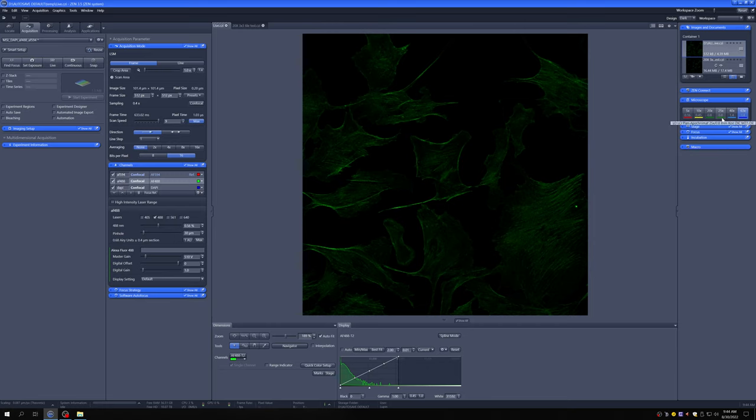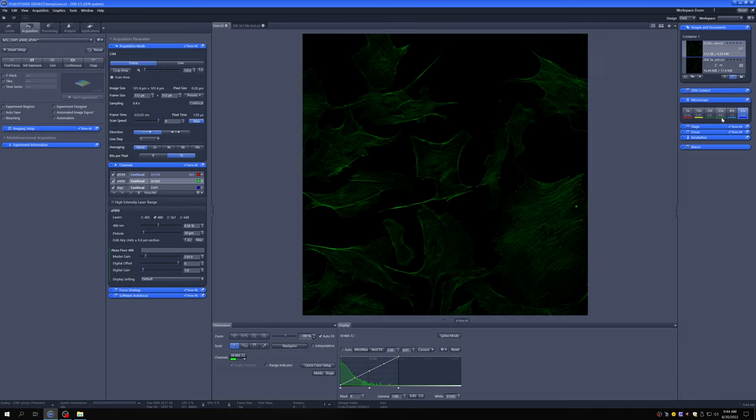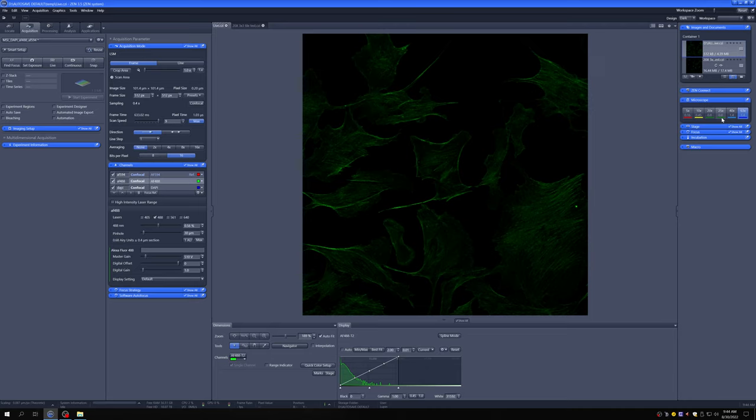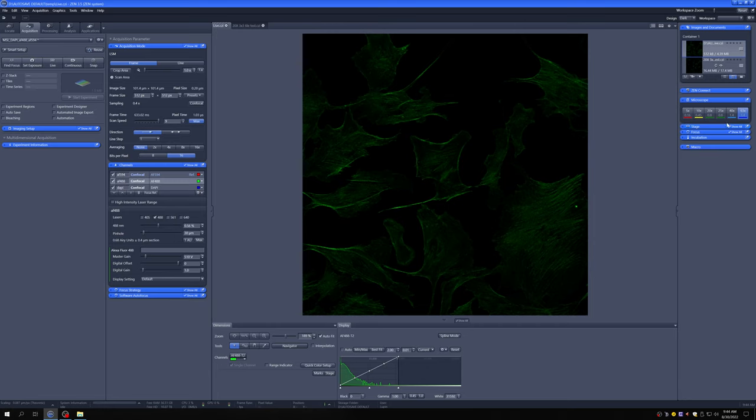The 25x is kind of a special objective in that it can use three different kinds of immersion oil, and it's typically used to image things like organoids. It has a 0.6 millimeter working distance, so it can look at something pretty thick, and it can use an immersion medium that matches the refractive index of the sample as much as possible. If any of you are doing organoids, let me know, and we can discuss more how this objective can be useful for you.